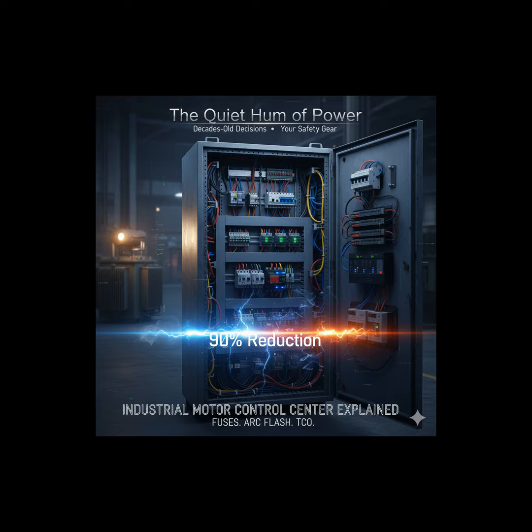So you isolate the problem. Exactly. If a motor in the basement has a short circuit, you want only that specific combination starter's fuse or breaker to open. You do not want the main power coming into the whole MCC to trip, because if that happens, you shut down every motor in the facility, potentially including life support systems or critical HVAC. The NEC handbook often favors current-limiting fuses in these applications because their precise, fast operation makes achieving this coordination much more reliable than with standard breakers.